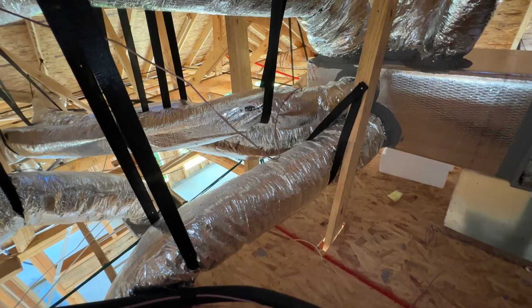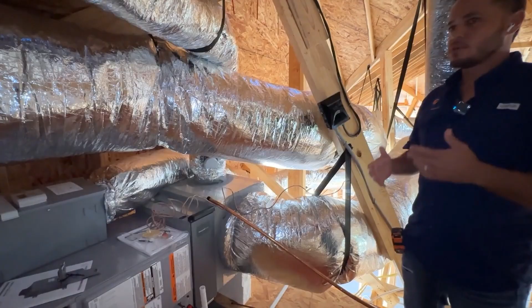Here in the city of Austin, you'll be required to have an R8 duct. R8 means 2-inch insulation, for every duct, big or small. You can get away with R6 on the return side here in Austin, but we always do R8. Bigger or better insulation will never hurt the system - it's actually more efficient and works better for you. So even though the minimum is R6, you're going with R8 for quality. Yeah, we always go above and beyond. The pricing difference between R6 and R8 duct isn't much, so we always use only R8.